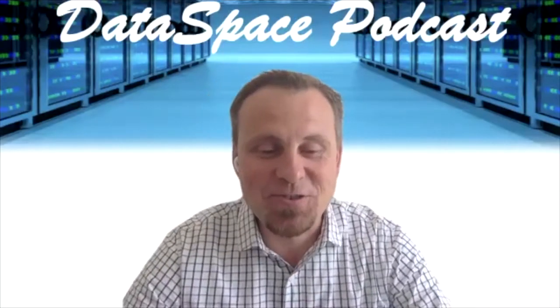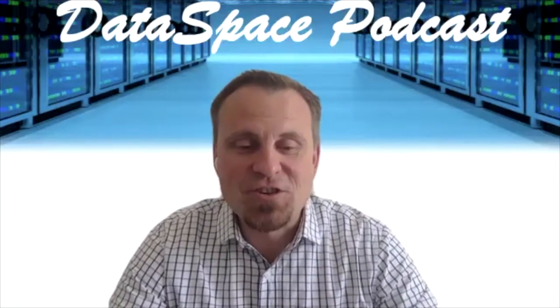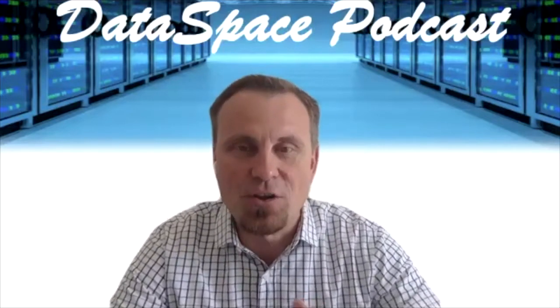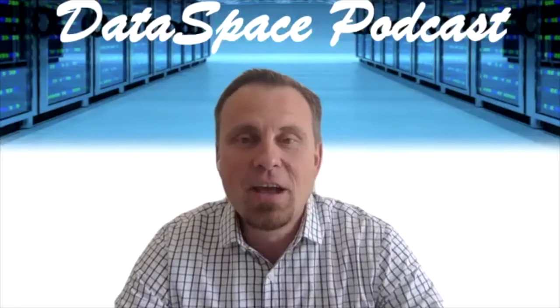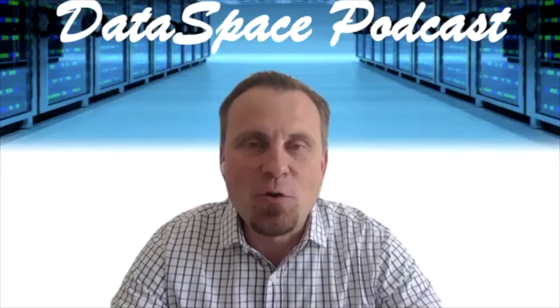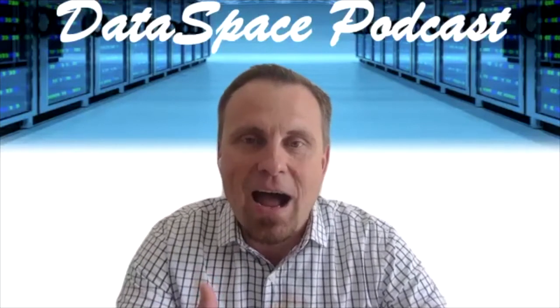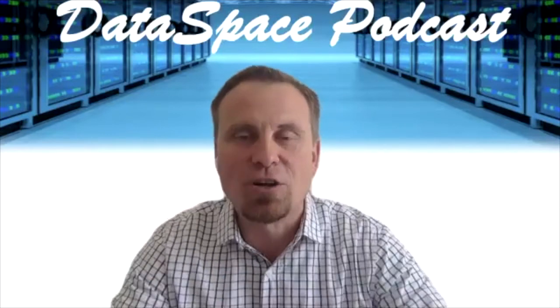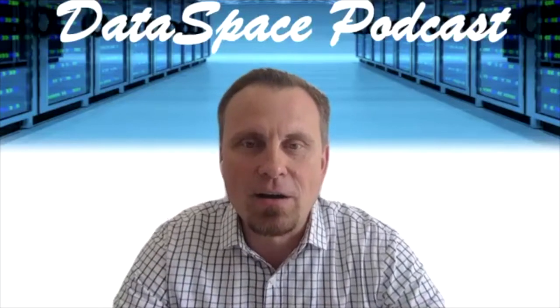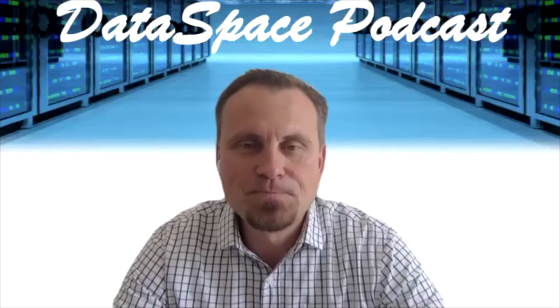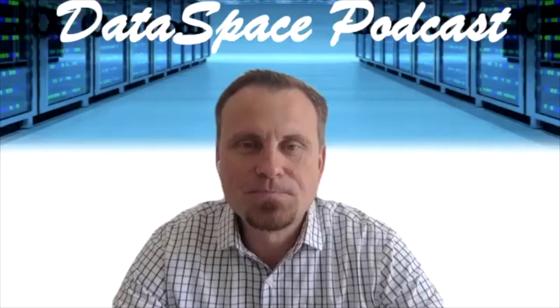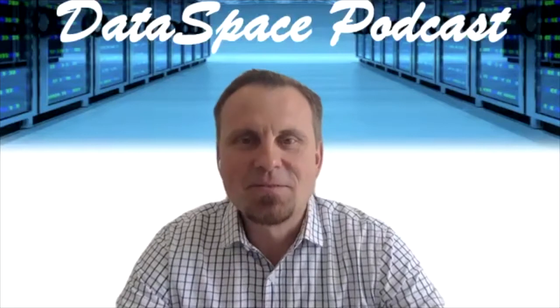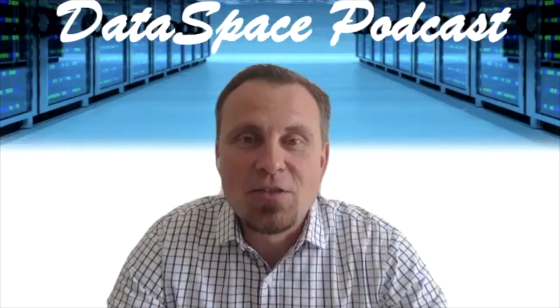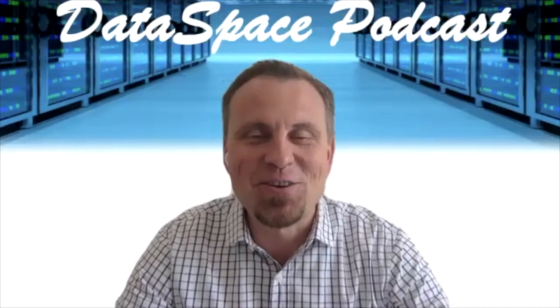Absolutely, no, they're very, very interesting. It's interesting because, as you've mentioned, air handlers, water pumps, cooling towers, chillers - all of these use electric motors, and every one of these is utilized in data centers. And what you're saying is that each and every one of these can actually utilize these drives and therefore have much greater control than their current capability. Absolutely - much greater control, and with the proper technology, much cleaner power, which means higher efficiency and higher reliability. Right, which are the key terms in the data center industry today: efficiency and reliability.